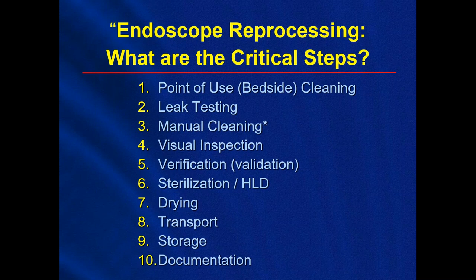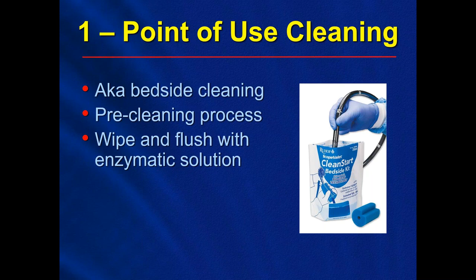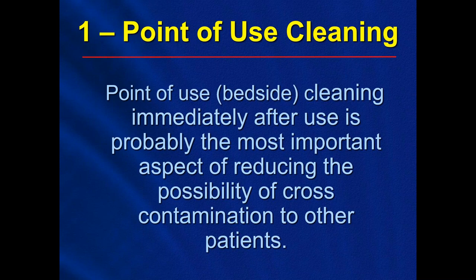So critical step number one is point of use cleaning, also known as bedside cleaning. This is a pre-cleaning process done before the manual cleaning. Basically, you're taking an enzyme solution, you're wiping down the outside of the scope, you're sucking some of that enzyme solution through any channels, suction channels, any lumens that may be in the scope. You want to get that enzyme solution inside and outside of this scope so that it starts the cleaning process. Now, point of use cleaning immediately after use is probably the most important aspect of reducing the possibility of cross-contamination to other patients. Why? Because this initial immediate cleaning to remove bioburden will prevent the formation of biofilm, which has been associated with cross-contamination to other patients.